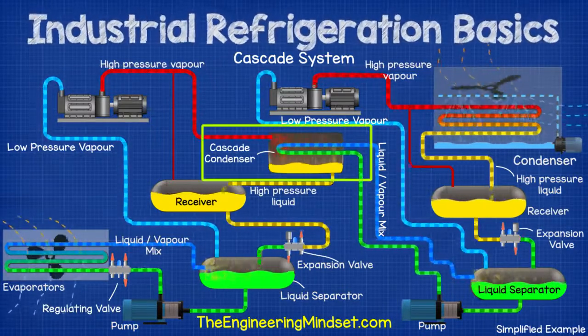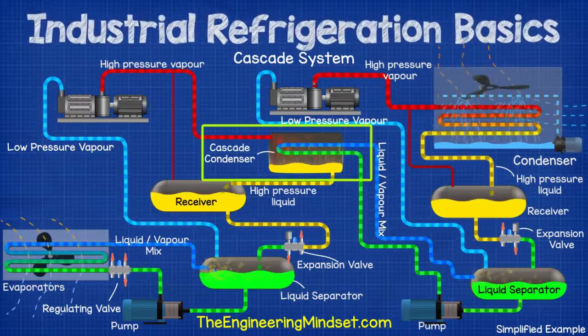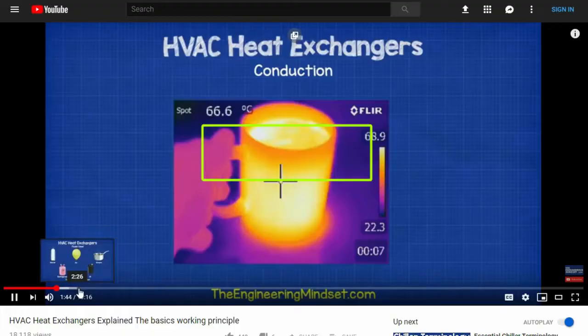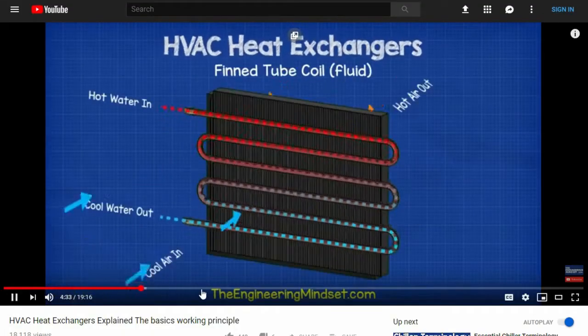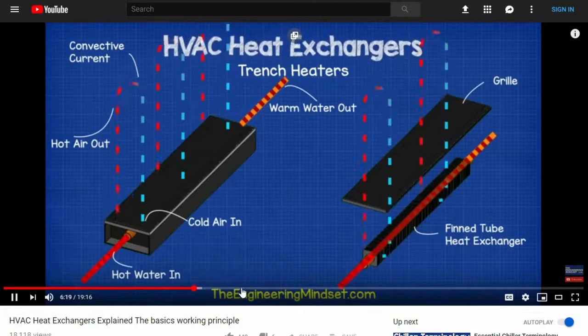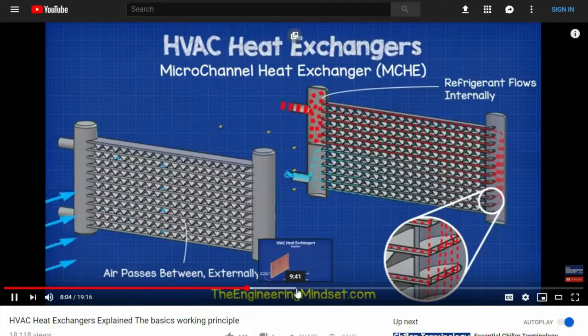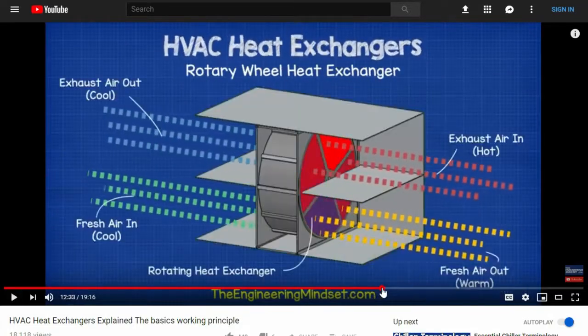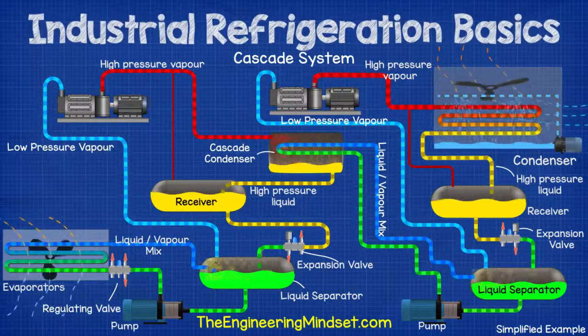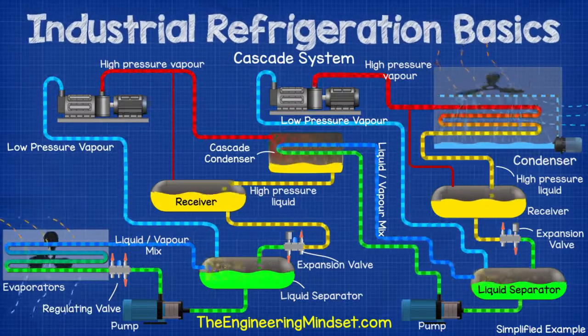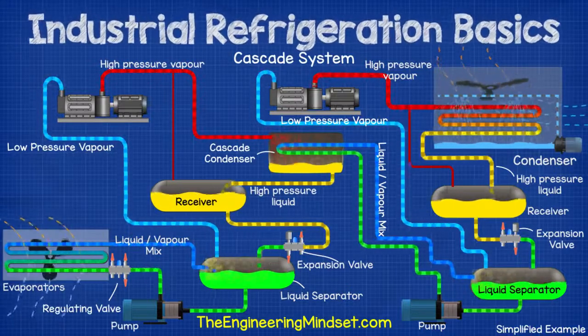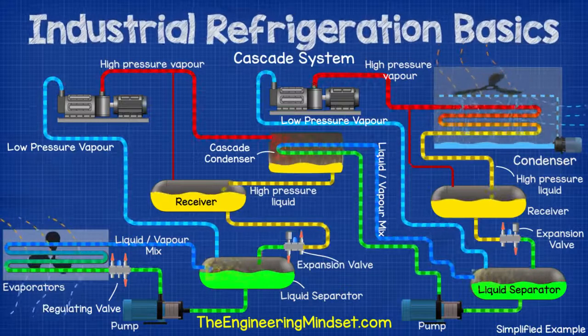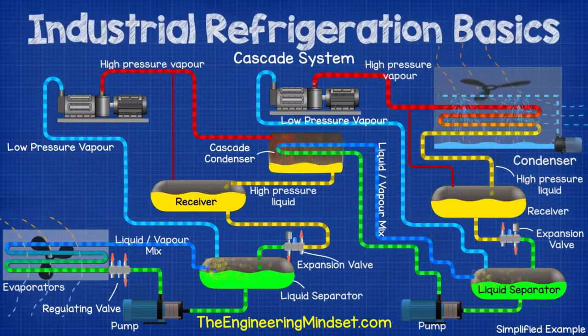Connecting the two circuits is a heat exchanger known as a cascade condenser. We've covered how heat exchangers work as well as the different types in our previous videos — do check that out, links are in the video description down below. The cascade condenser acts as a condenser for the high temperature circuit, but also an evaporator for the low temperature circuit.